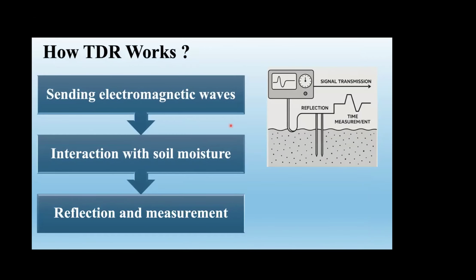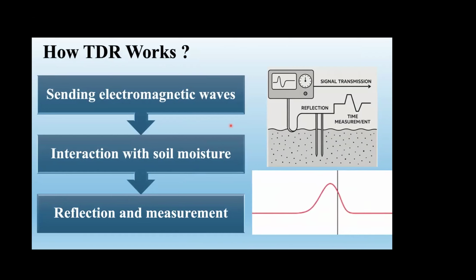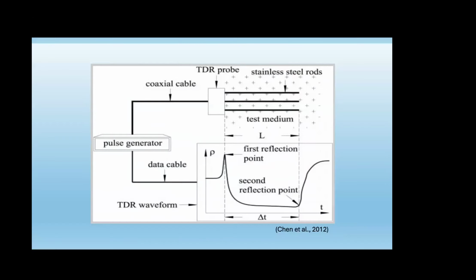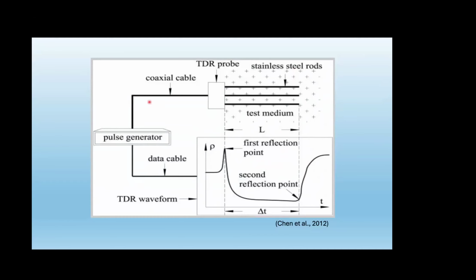TDR works in three basic steps, the first of which is sending an electric pulse. The TDR sensors have metal probes, and here you can see in the figure that they send high frequency electromagnetic waves into the soil. The second step is interaction with soil moisture. The pulse slows down when it encounters the water in the soil due to water's high dielectric permittivity. In step 3, reflection and measurement, the sensor measures the pulse's return time to determine the soil moisture content. To give a clear idea, we can see in this figure how this actually works in detail.